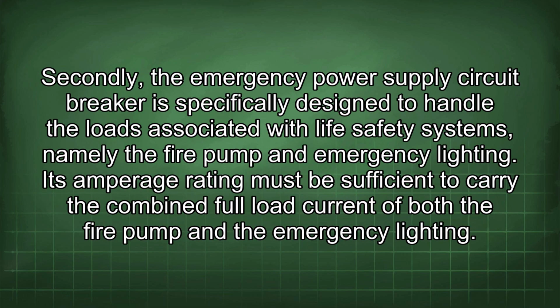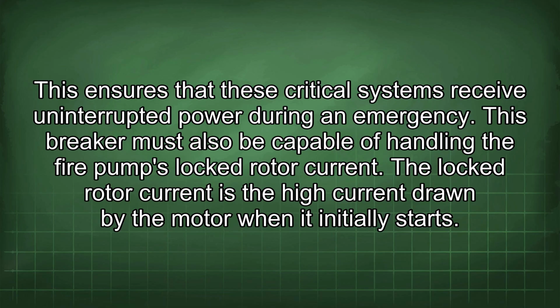Secondly, the emergency power supply circuit breaker is specifically designed to handle the loads associated with life safety systems, namely the fire pump and emergency lighting. Its amperage rating must be sufficient to carry the combined full load current of both the fire pump and the emergency lighting. This ensures that these critical systems receive uninterrupted power during an emergency. This breaker must also be capable of handling the fire pump's locked rotor current.